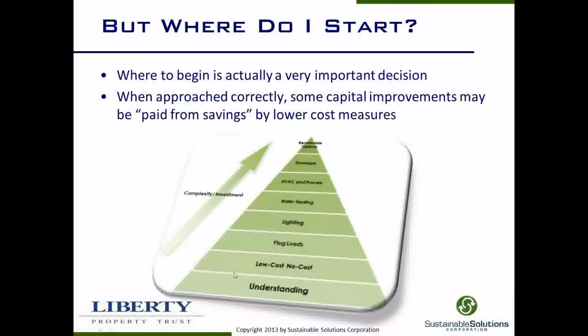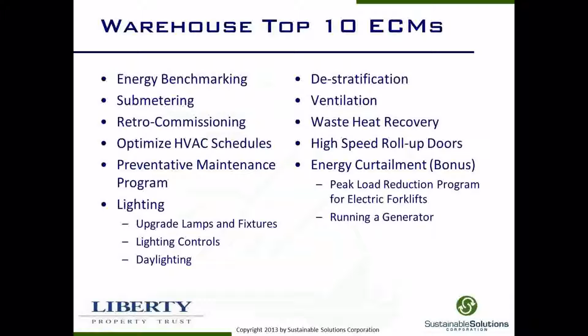But if you're looking at low cost and no cost measures, you can do simple things like changing your operating schedule or using programmable thermostats. Those things typically don't cost much and usually result in big savings. Once you achieve savings from lower cost measures, you can use that money to do capital improvements within the building. So maybe there's an opportunity to reduce costs by turning things off or changing schedules, and then those savings can be used to upgrade lights, buy Energy Star equipment, or even improve the HVAC system.